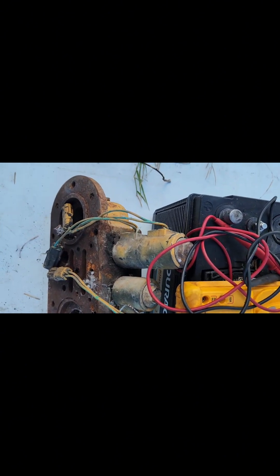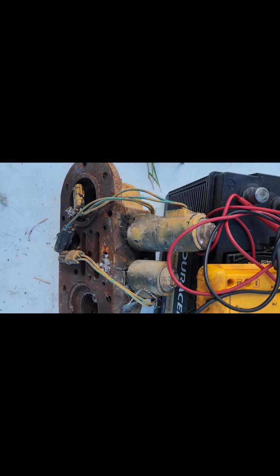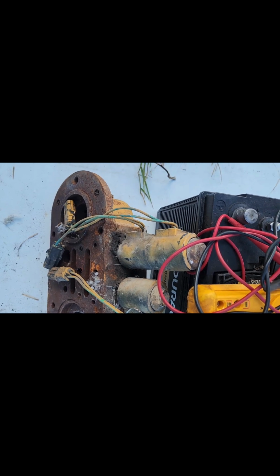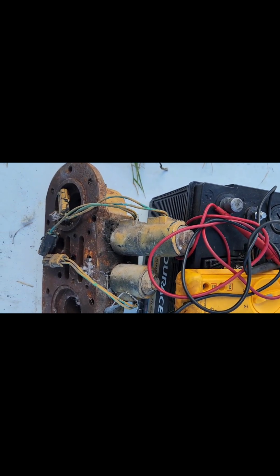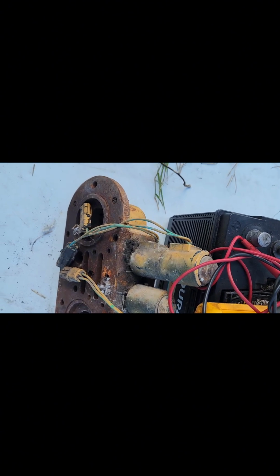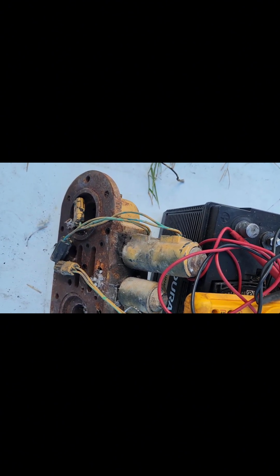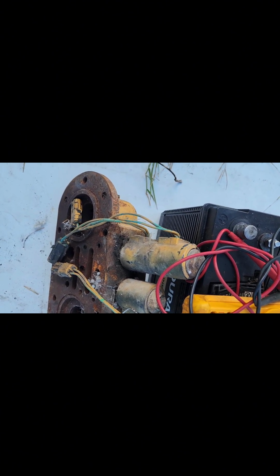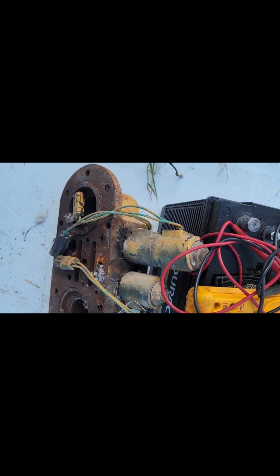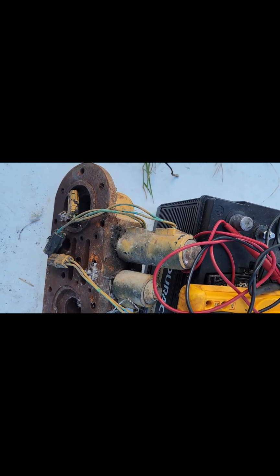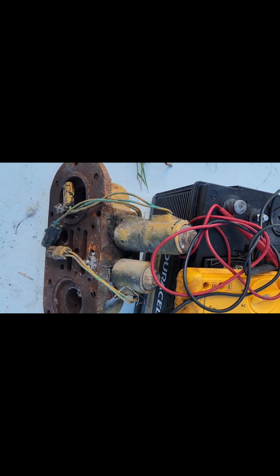Now, each manufacturer is different. Depending on how many turns you have in the coil, that will determine what the resistance is. So to determine if a coil is good or bad, normally you check the resistance. Most are from 0 to 5, or 0 to 10, 5 to 10. This particular coil here, most of the time you have to get a hold of the manufacturer to find out what it's supposed to be.